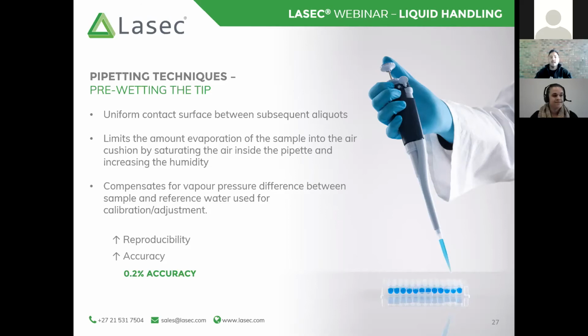What I would hope becomes quite apparent in this section as well is that there are different tools available. If you are feeling like even after pre-wetting, you're still noticing some level of evaporation, some dripping, or some skewed results, you might want to consider a positive displacement pipette, where we've eliminated any need to prime. Okay, the only reason to pre-wet a positive displacement pipette would be for the first point of creating a uniform contact surface for your solutions.